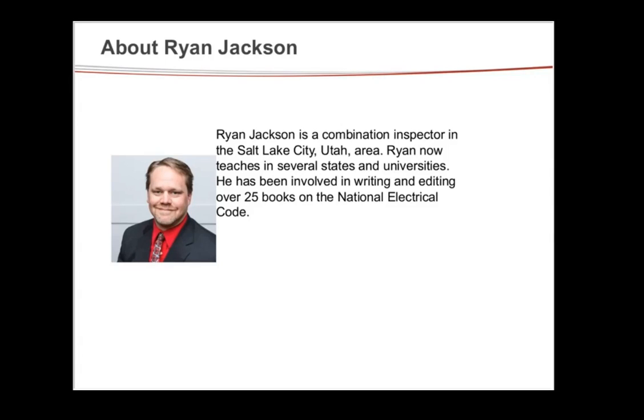No, and I don't think it will happen because the scope is so different. The scope of the code is the equipment and the installation, and the scope of NFPA 70E is how you work on the equipment. Now, we try to make sure that the rules don't contradict each other because that's obviously a bad thing, and we certainly borrow language from one another, especially with that warning label rule we just talked about. A lot of times what happens is we'll change NFPA 70E to add safety requirements like labels, and then we'll take those rules and put them into the NEC. But as far as marrying them into a single document, I don't think that will happen.